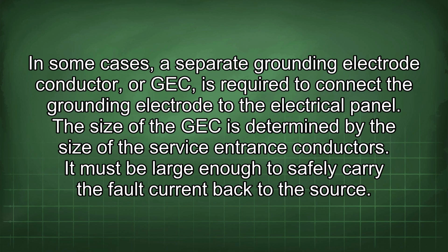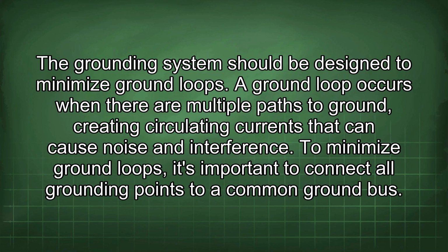The size of the GEC is determined by the size of the service entrance conductors. It must be large enough to safely carry the fault current back to the source. The grounding system should be designed to minimize ground loops. A ground loop occurs when there are multiple paths to ground, creating circulating currents that can cause noise and interference.